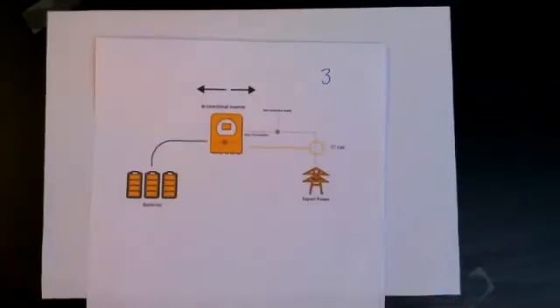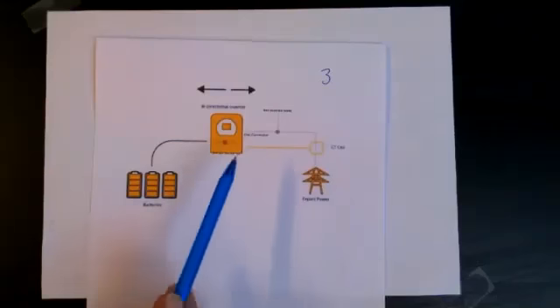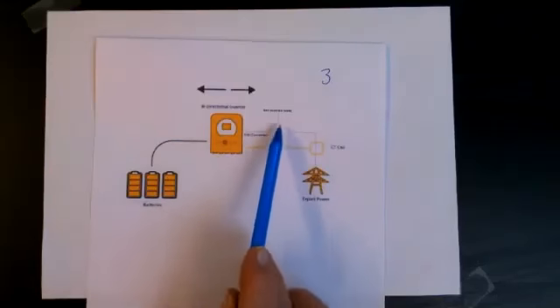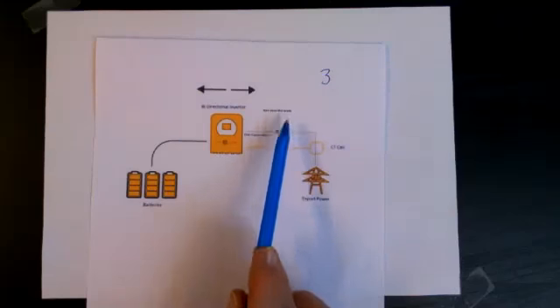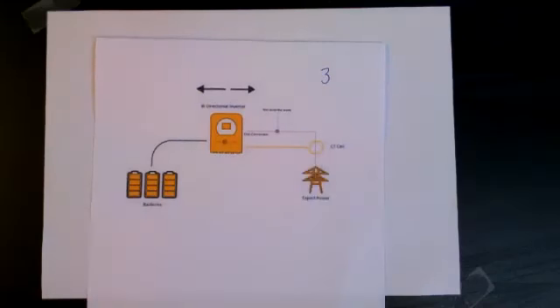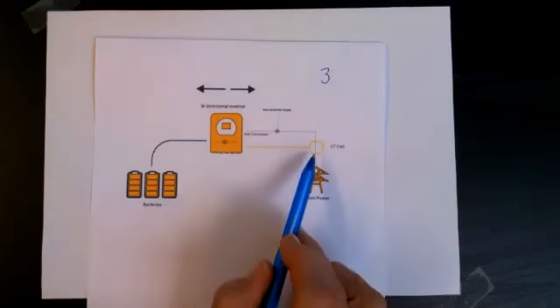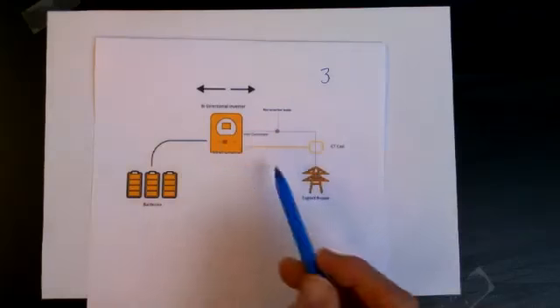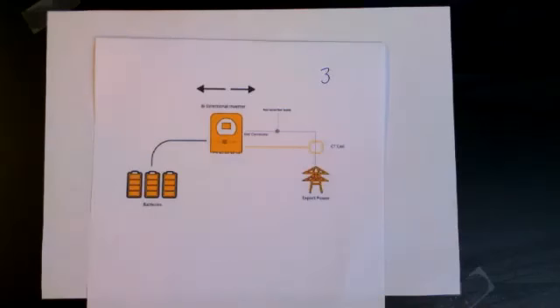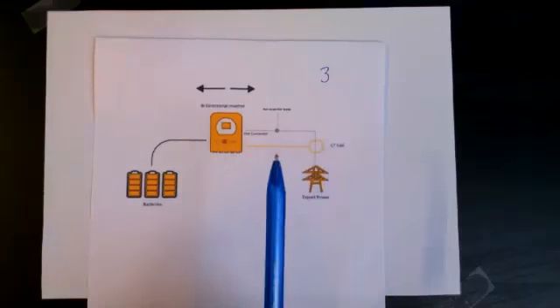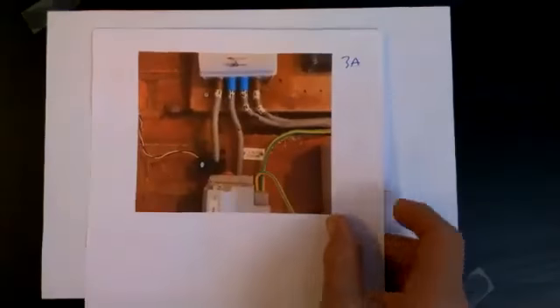One of the things I was trying to emphasize before is the inverter, which is the bi-directional inverter. So here is your grid connection, and this is your non-essential load connected here. And basically the CT coil, because a lot of people forget about the CT coil and think, oh, it's not important. It is the most important part of the inverter. CT stands for current transformer, and basically this is the thing that controls it. If you don't have a CT coil, then it will just go back and export to the grid, and it'll have uncontrollable export. You can't control it.